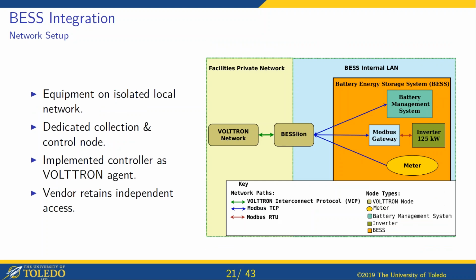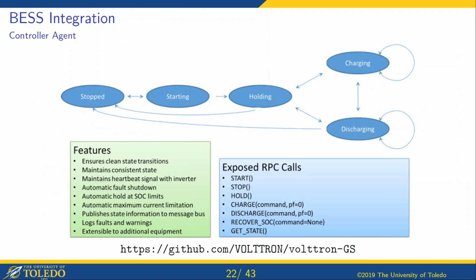Now the battery system is brought in a similar manner. We have a Raspberry Pi sitting in the field. As with the PV array, it has two network ports, one on a private network that doesn't touch the rest of our facilities network, and one on the facilities network where it can talk to the rest of VOLTTRON. For the battery system, we have the top level controller running as an application, an agent as it's called in VOLTTRON, taking data from the battery system, the inverter, and the meter, and sending back control signals.